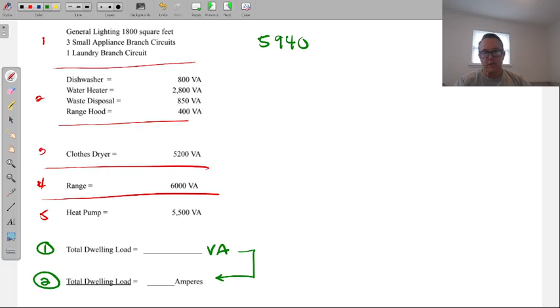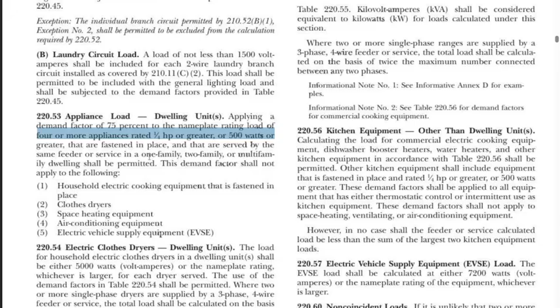All right, part 2, or section 2, and we'll put VA just to remind ourselves of what it is. So section 2, these are our fixed in place appliances. This is Article 220.53, appliance load, dwelling unit, and this is the one that allows the 75% if two things are met: 4 or more appliances, and all of them at 500 watts or more.